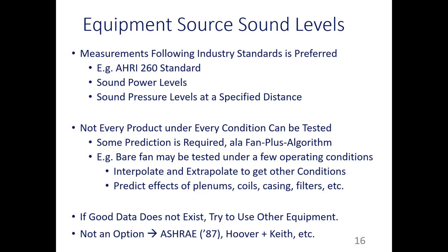We talked about how we want to get noise data that was from a laboratory test. And if it's a laboratory test, or even if it's a field test, sometimes field tests are done too, you want to follow the industry standards. There are lots of different standards. The American Heating and Refrigeration Institute, they publish a lot of different standards. I think most of their standards are free. Sound power levels is what you'd want. Sometimes you get sound pressure levels at a specified distance. I would prefer sound power levels. If you have this, then you can just insert it into your model for whatever the environment is.